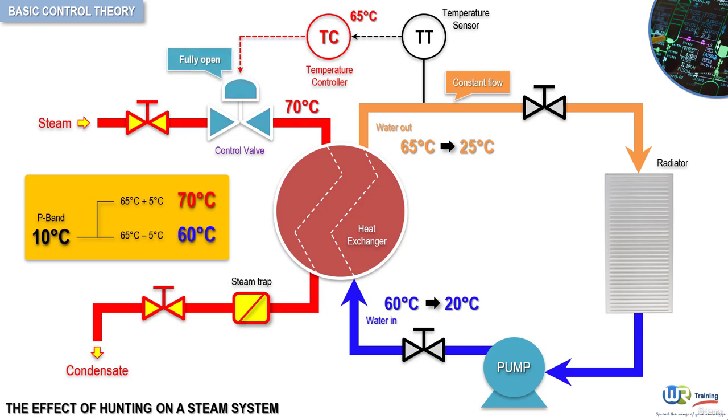As a result, the steam temperature is observed to increase from 70 degrees Celsius to 140 degrees Celsius almost instantaneously. What is the effect on the water temperature and the stability of the control system? To answer this question, we're going to use the heat and the steam load relationship.